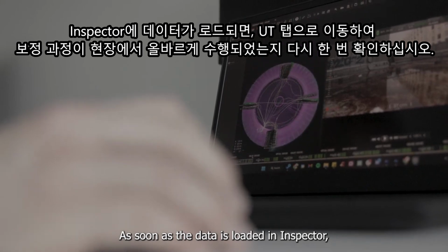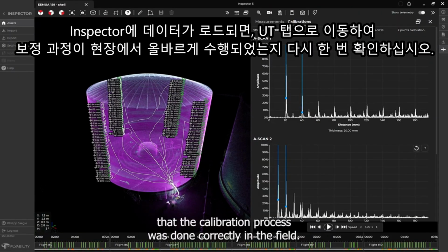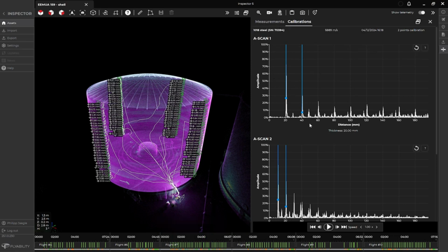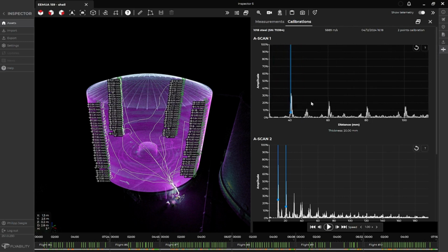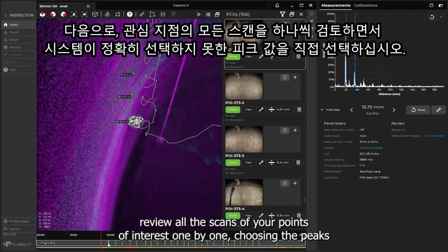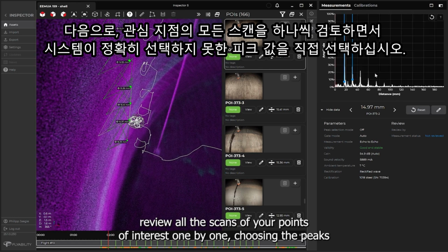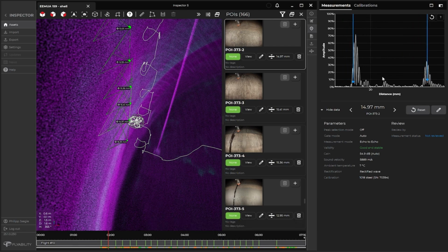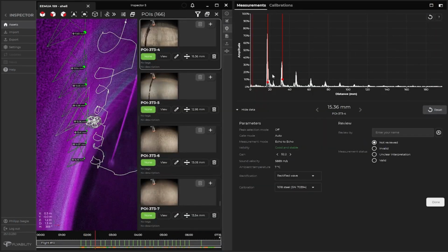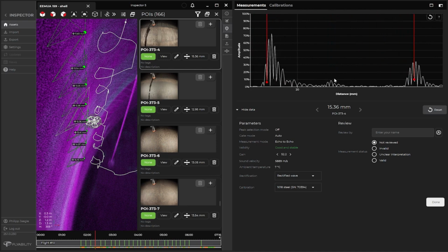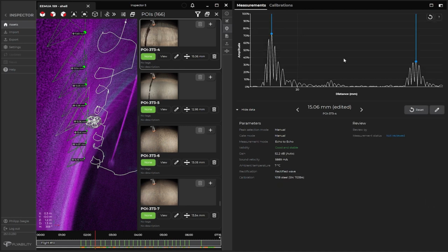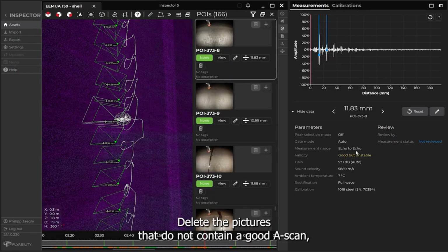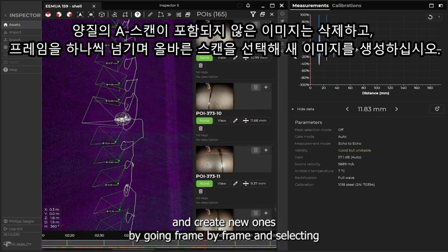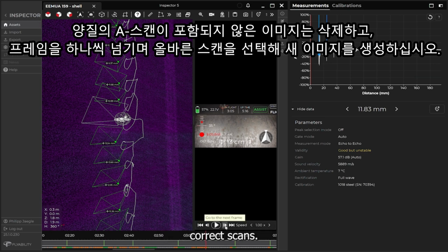As soon as the data is loaded in Inspector, go to the UT tab and check once more that the calibration process was done correctly in the field. Next, review all the A scans of your points of interest one by one, choosing the peaks that were not correctly selected by the system. Delete the pictures that do not contain a good scan and create new ones by going frame by frame and selecting correct scans.